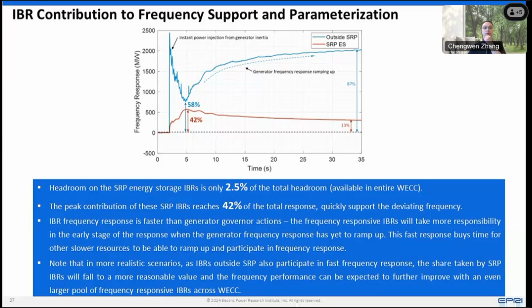If we don't have this very fast response from the SRP battery storage systems, the frequency nadir can drop very fast in the first few seconds while generators are still trying to ramp up. But in the future, in reality, we will have frequency response from IBRs outside of SRP. Once we have that, we can expect even better frequency dynamics, because we'll have a larger pool of IBRs capable of the same fast, strong response to the system.